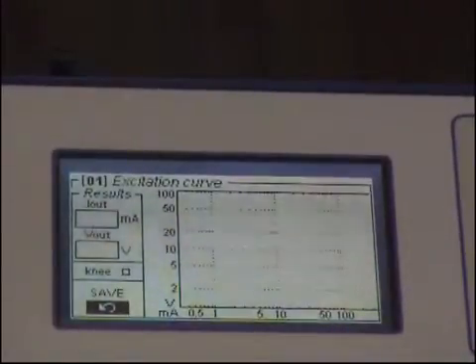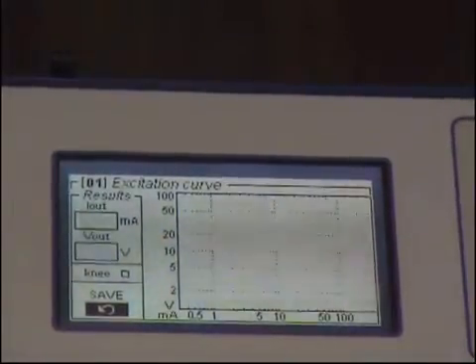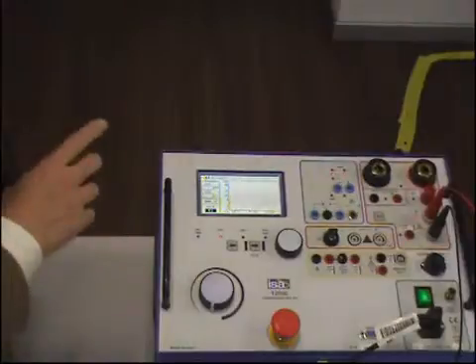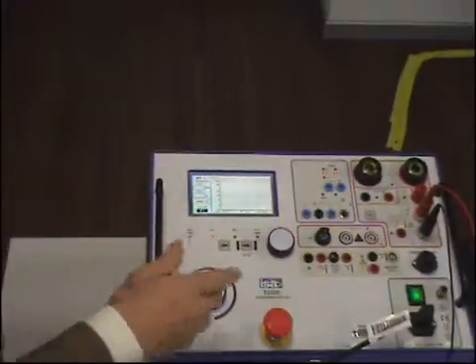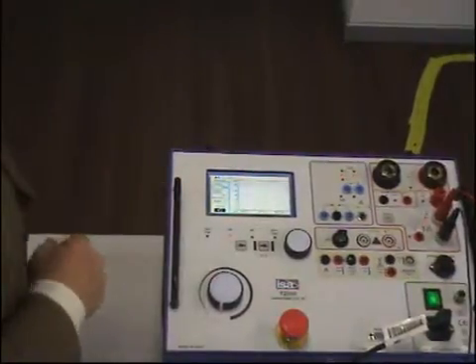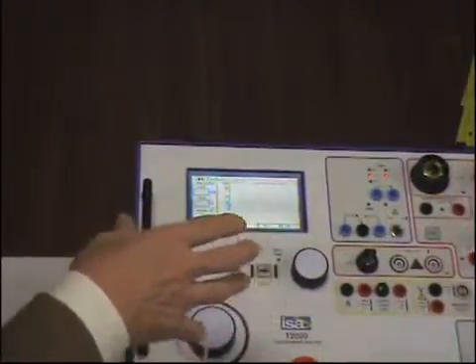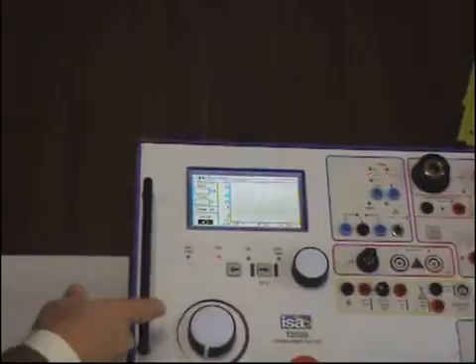You have to move the current control knob slowly, because otherwise you would cause some saturation effect on the current transformer that will also cause some shift on the knee point. The knee point will not change very much if you are slightly faster, but if you are too fast it will change. The test set automatically recognizes the knee point given the IEC condition while you are going down with the current.